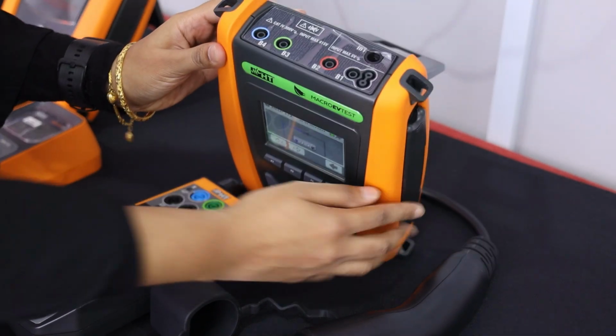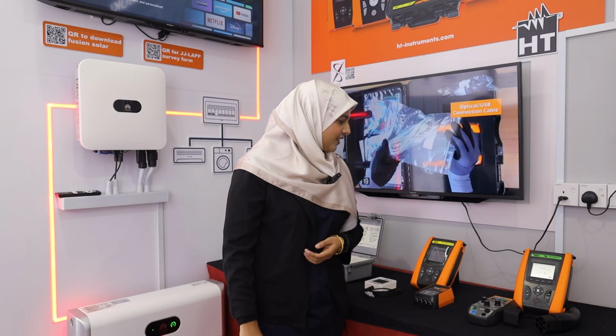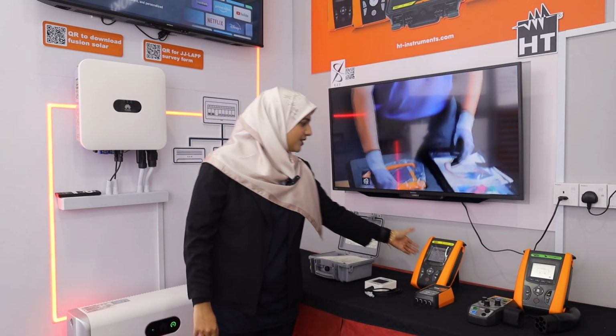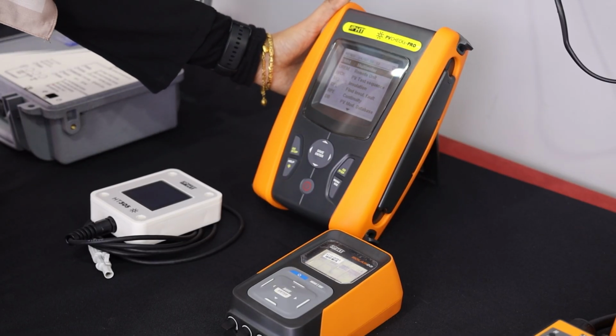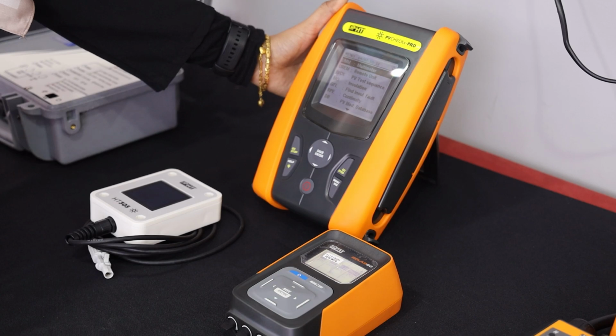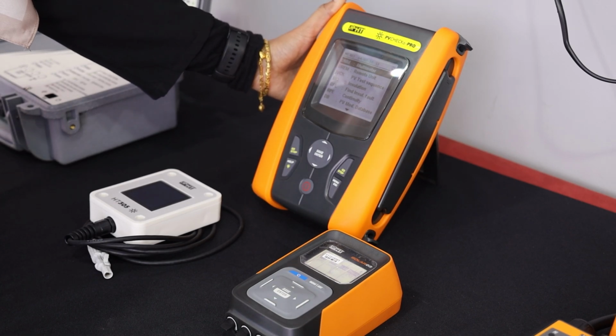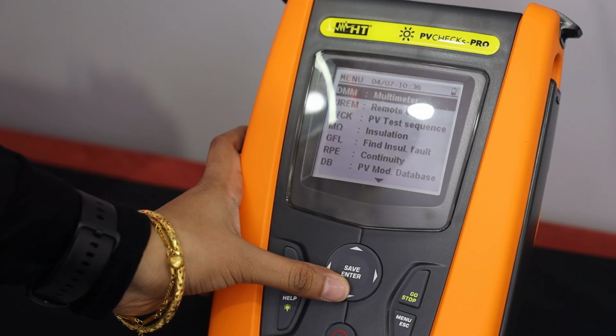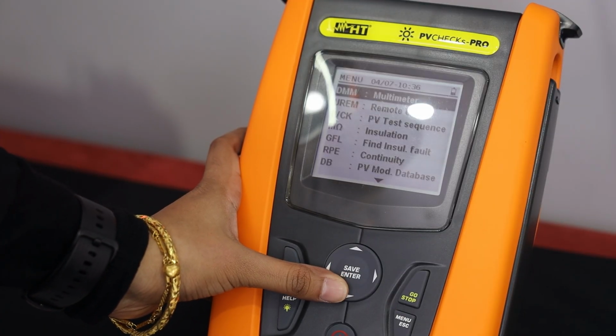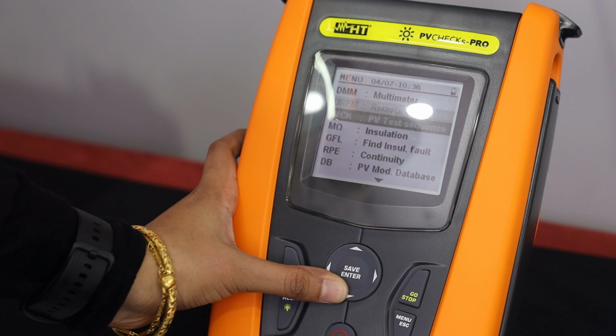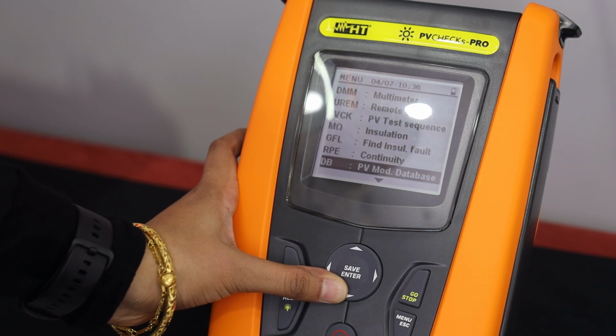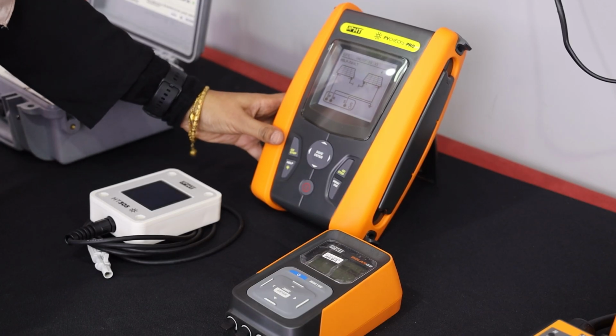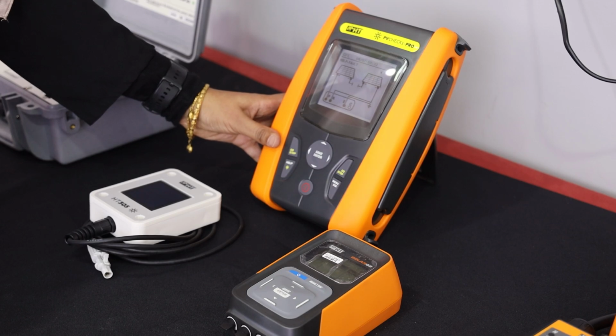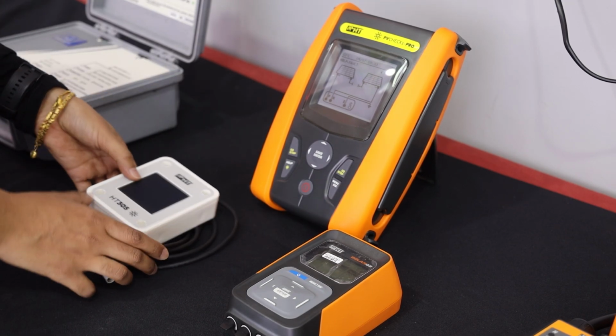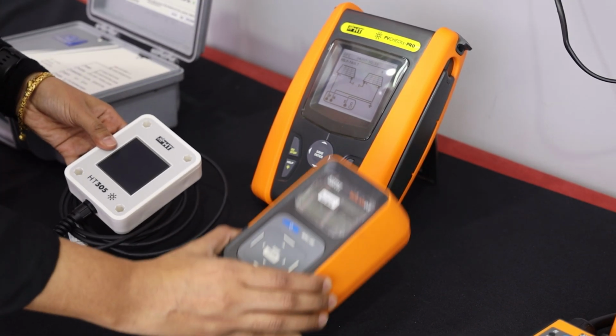Our second product, and most selling product, is PV Check Pro, capable of doing VOC up to 1500 volts as well as 40 amps current. This is the highest range in the Malaysian market. Our selling point for this product is it can do a ground fault test, which can locate poor string connections between panels. It comes with a reference cell as well as an irradiance sensor.